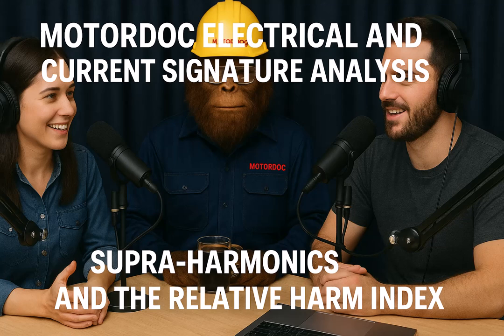Skin effect. Current crowds to the surface of the conductor, increases resistance, causes localized heating, potential damage to insulation, connections. Plus, eddy currents in motor cores, transformer cores, they get amplified. More energy loss, more heat. Bad for insulation. Exactly. Supra-harmonics also put more voltage stress on insulation materials, increasing failure risk. They generate electromagnetic interference, EMI. They can amplify capacitive currents, maybe creating new leakage paths. They can even cause resonance in circuits, interfere with power line communication systems, and damage sensitive semiconductor components in electronics. It's a whole list. That is a broad range of problems.